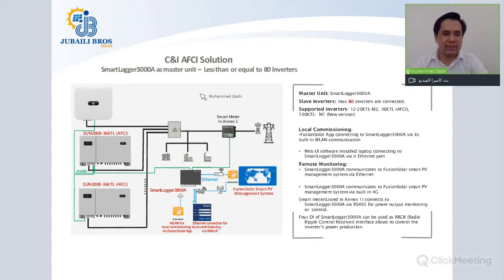If you have an AFCI solution requirement in a C&I or medium scale project, one option is that you have a Smart Logger 3000A as a master unit, and you are using less than or equal to 80 inverters. In this scenario, you must use only those inverter models which can support the AFCI feature. As discussed, these are from 12 to 20 kilowatt size, the 36 KTL with AFCI model, and the 100 kilowatt size. So slave inverters can be up to 80 devices, and local commissioning is through FusionSolar or the Web UI, and remote monitoring through the FusionSolar app or the web monitoring.